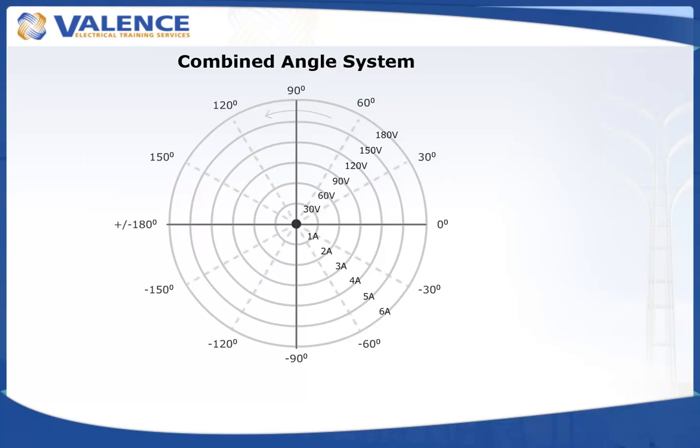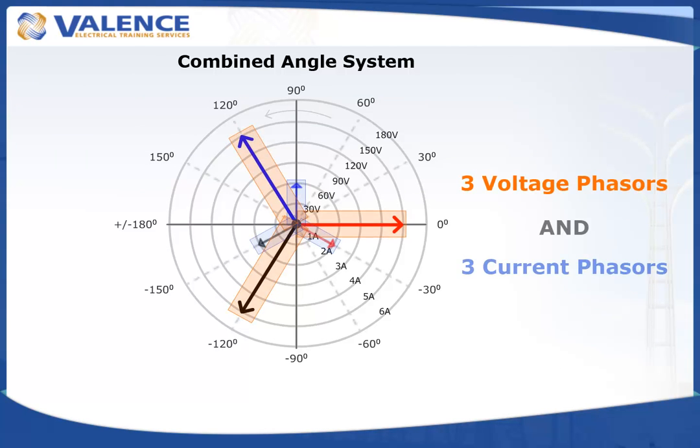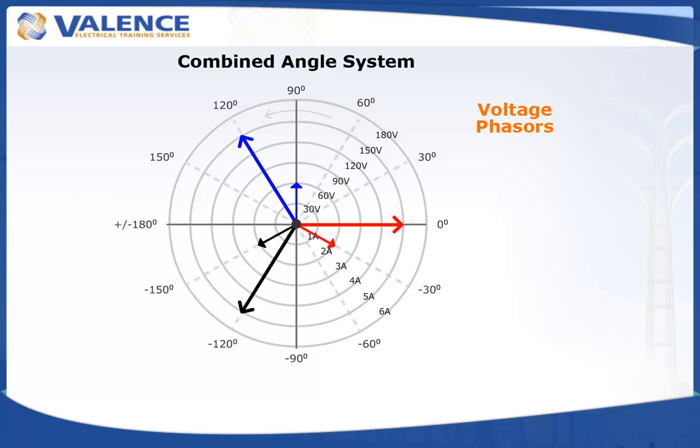Phasor diagrams usually include three voltage phasors and three current phasors, which are plotted in groups with different scales. The procedure for plotting multiple groups on a phasor diagram is the same once you choose the angle system you want to use, but we use different arrowheads to indicate which signal group each phasor is in. Voltage phasors are typically plotted with open arrowheads, and current phasors are typically plotted with closed arrowheads. You should always have some visual cue when different types of phasors are plotted on the same diagram.